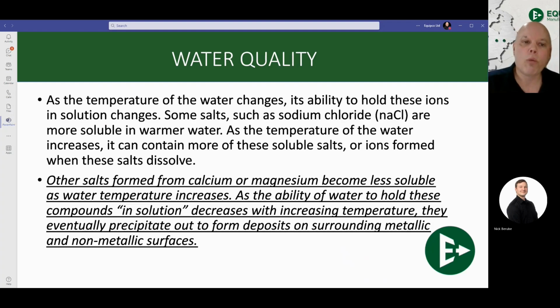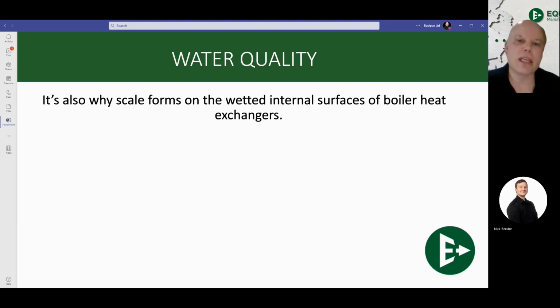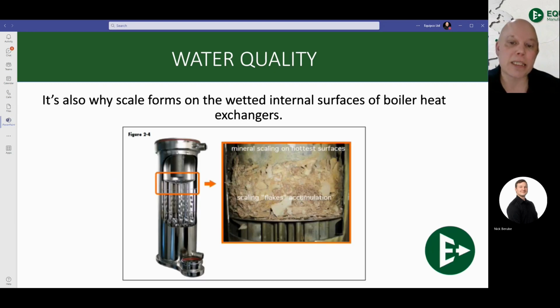Now inside that water we have these mineral salts. That's what they're called. Like your calcium ions are called salts. So calcium ions, magnesium ions. What happens is these salts become less soluble, meaning that they come out of solution as the water temperature rises. As the water temperature goes up, these mineral salts come out of solution and they start to stick and create deposits on any metallic and non-metallic surfaces, but just as long as it's hot, they like to stick to that. The hotter the area, the more it's going to come out of solution, the more buildup you're going to get inside of those areas. This is why scale is formed on the inside of heat exchangers.